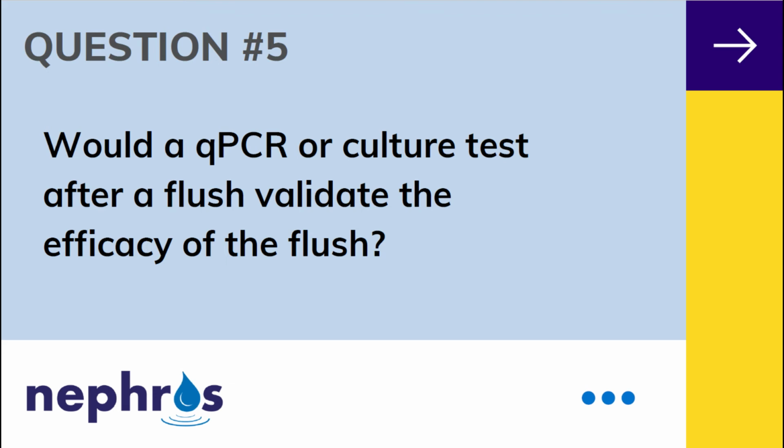Most water bacteria that are of a classification of gram-negative stain can double in 20 minutes, whereas other kinds of bacteria like Mycobacterium take a lot longer to be growing up. It takes 24 hours to double. So we really need to think about how we're going to validate the system for that flush. Do you culture it or do you use a PCR? If you're in a hurry, PCR really goes well.